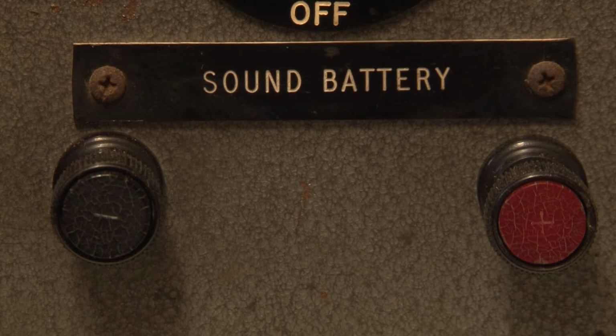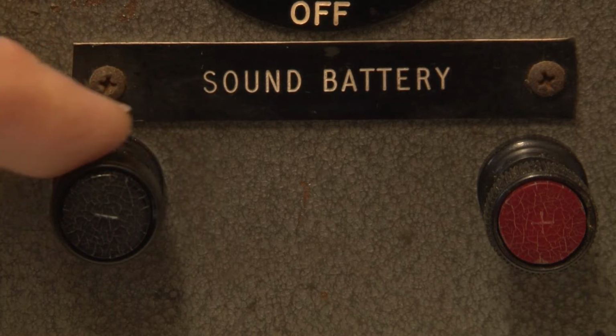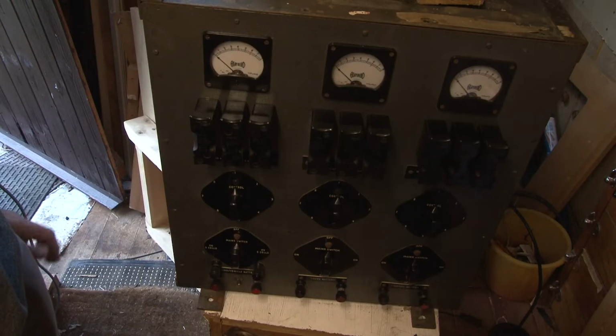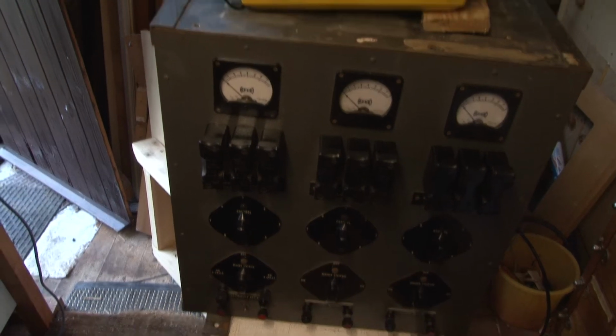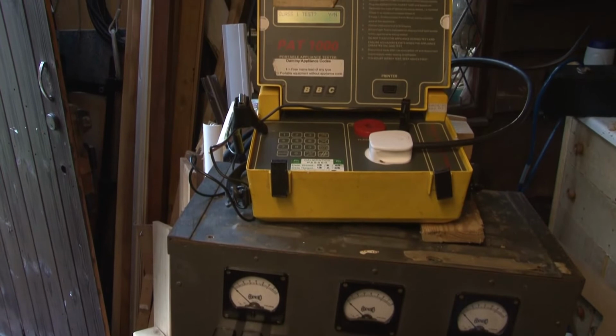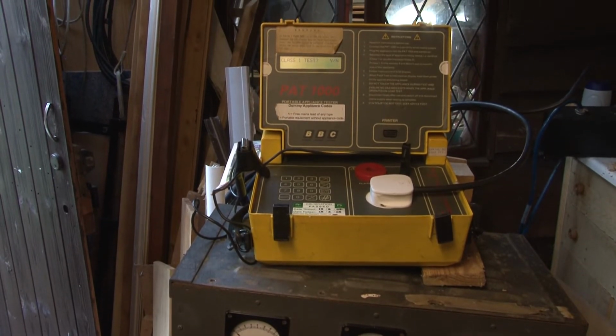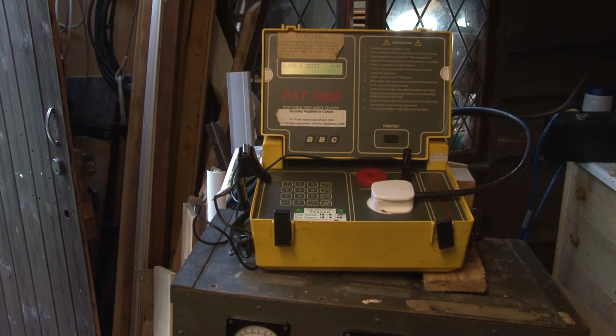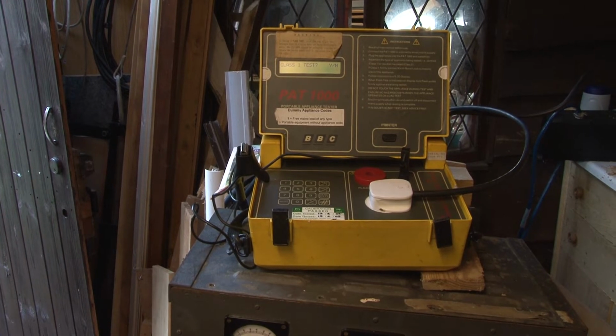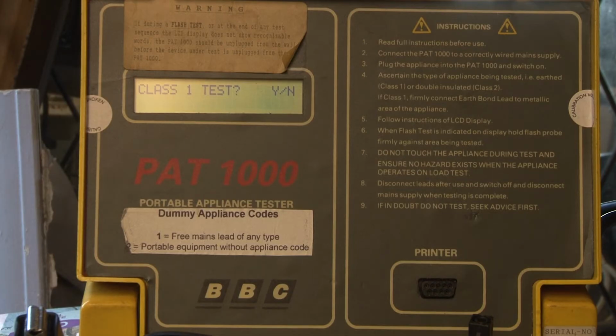So now it's time to do some electrical safety tests before we actually go ahead and power up the unit. But for that we're just going to use a portable appliance tester, which will do the basic tests required, just to check that this thing is actually going to be safe to use. Now, because this charger is basically a big metal box, that's what's known as a Class 1 piece of equipment, and it requires an earth test.